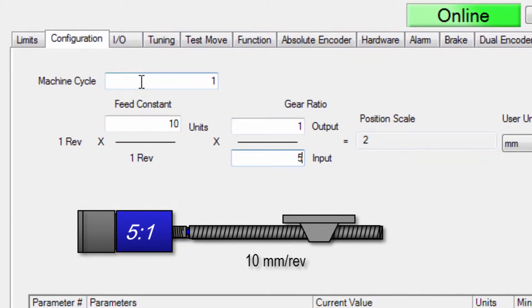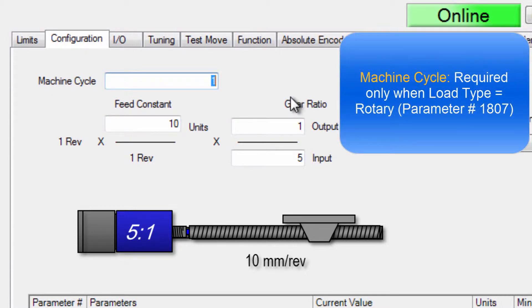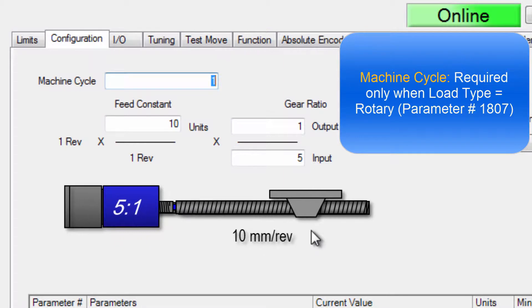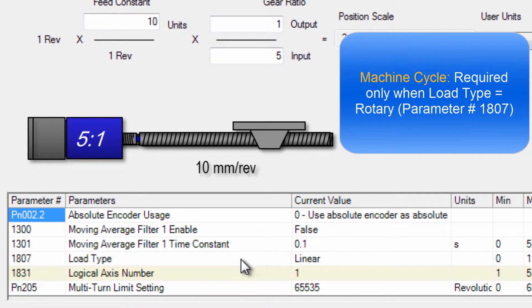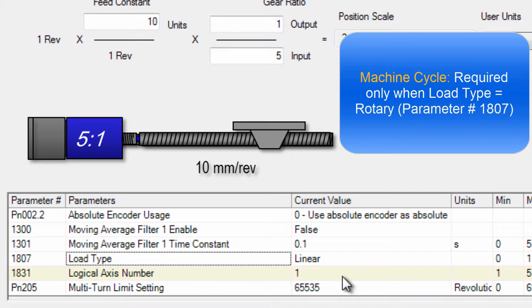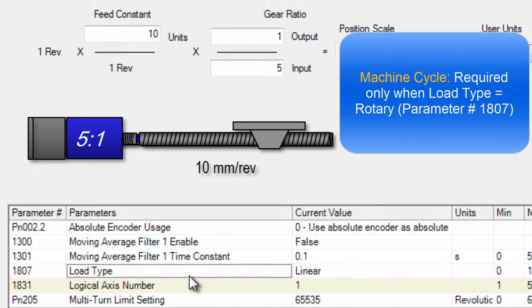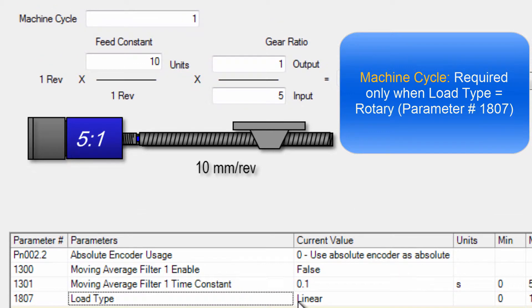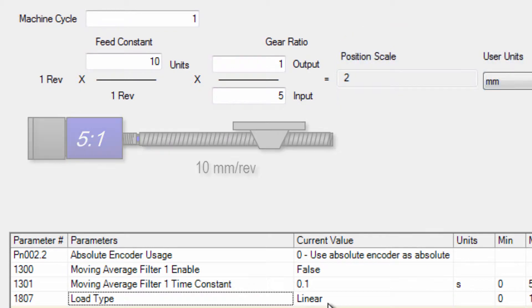Now I skipped over the top field here machine cycle because machine cycle is only used when the load type is set to rotary. The load type is down here parameter 1807. The load moves linearly for a limited distance and so the machine cycle does not apply when you have a linear axis.